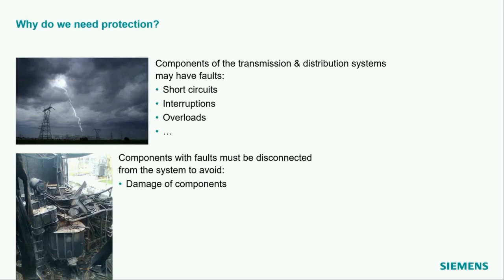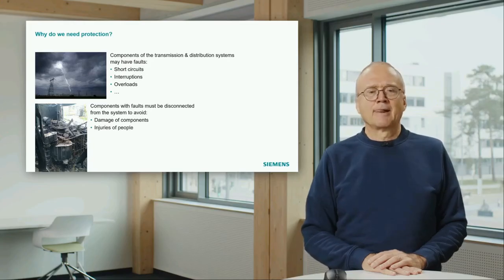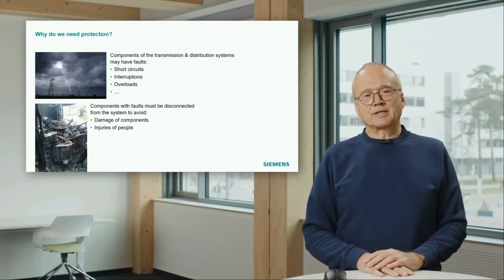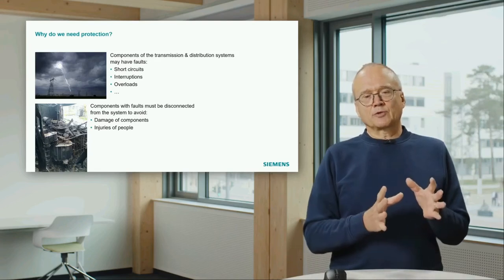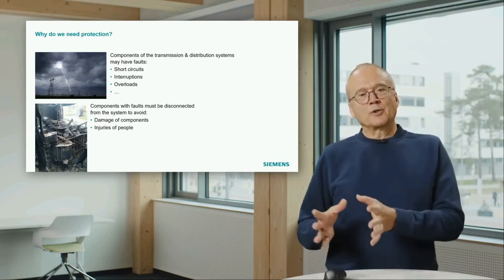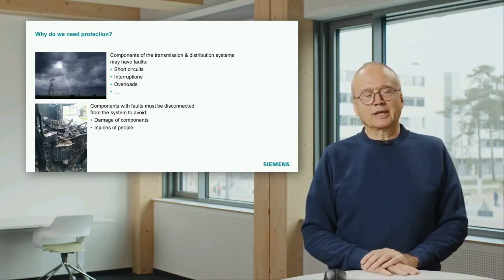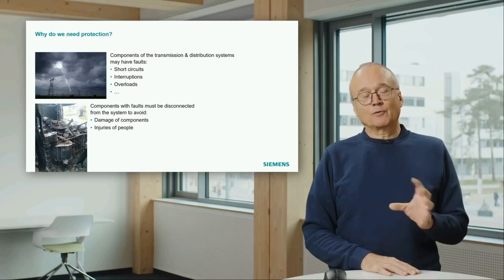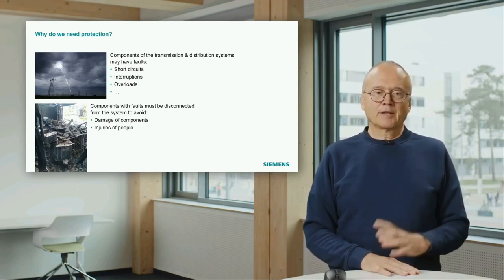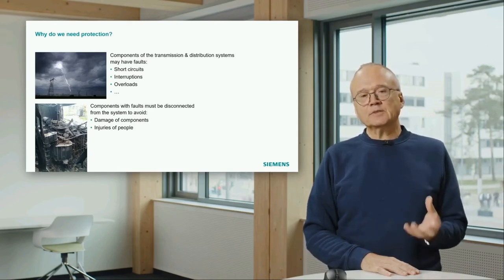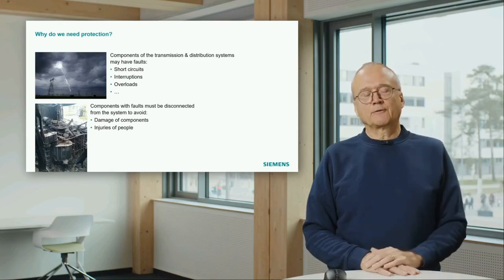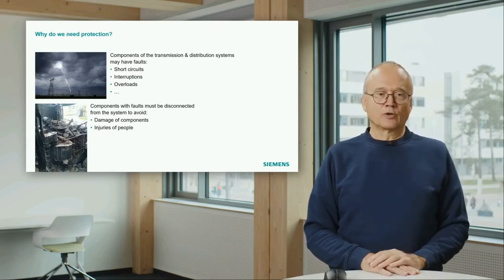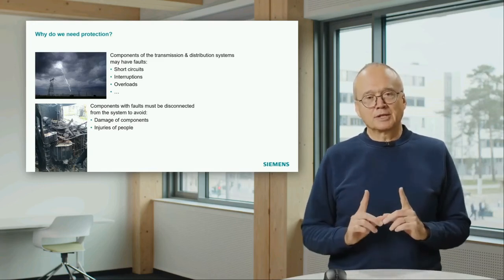This nice picture shows such a situation. That is a picture from a real case. What you see here used to be a brand new transformer. During the commissioning phase, the different teams had some misunderstanding. That means in this case, the transformer was energized while the protection system was still not in operation. And unfortunately, this transformer had a problem in the bushing. That means when the transformer was energized, there was a short circuit in the bushing, big current flowing, and what you see here is the result of that, because the protection didn't work.